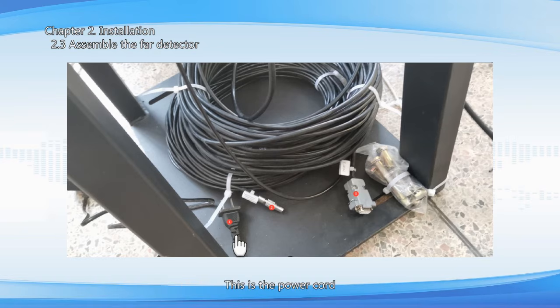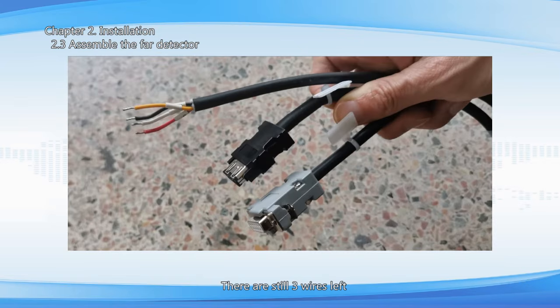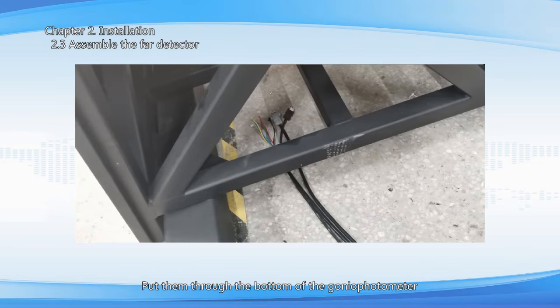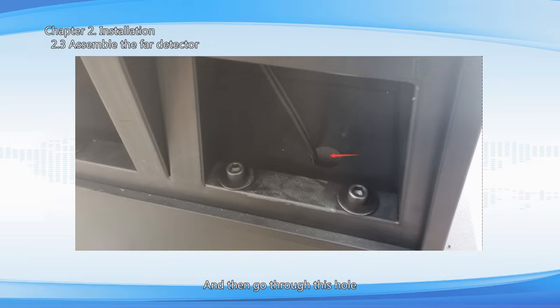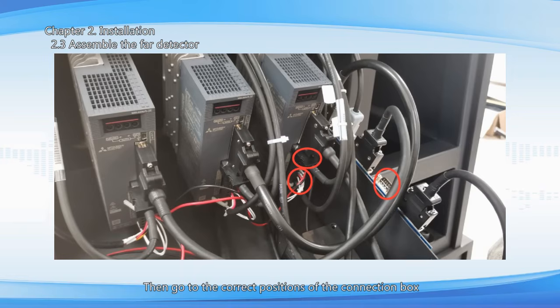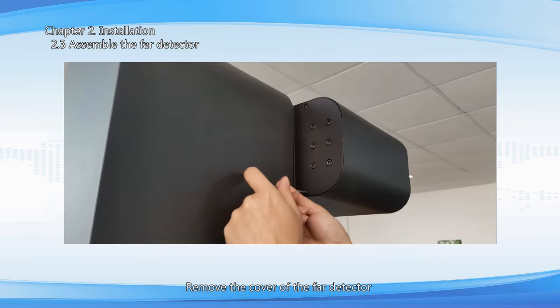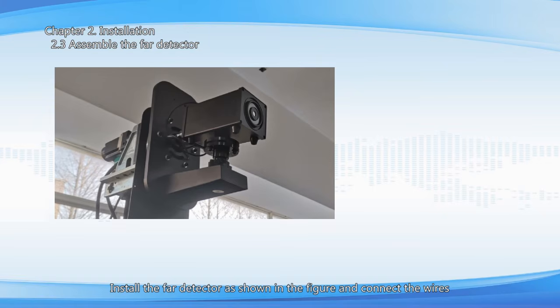This is the power cord. This one goes to the goniophotometer according to the wiring diagram. The port 3 communication cable goes to the communication box inside of the cabinet according to the wiring diagram. There are still 3 wires left. They need to be connected to the wires connection box of the goniophotometer. Put them through the bottom of the goniophotometer, and then go through this hole. Then go to the correct positions of the connection box. Remove the cover of the far detector. Install the far detector as shown in the figure and connect the wires.